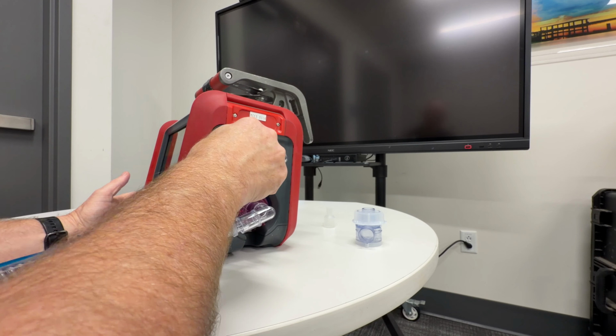All right, now we're going to have to change out our flow sensor, which we did. We're going to go neonate, we're going to go to pre-op check, and we're going to go to flow sensor. All right, I've already got our piece connected here on the ventilator tubing. So we go to flow sensor, connect or select it, and it's going to tell you disconnect patient. There's no patient connected, and now it's saying flip flow sensor. Take the whole thing off, flip the whole thing around, and that goes in there. Same thing applies. It's going to ramp up.